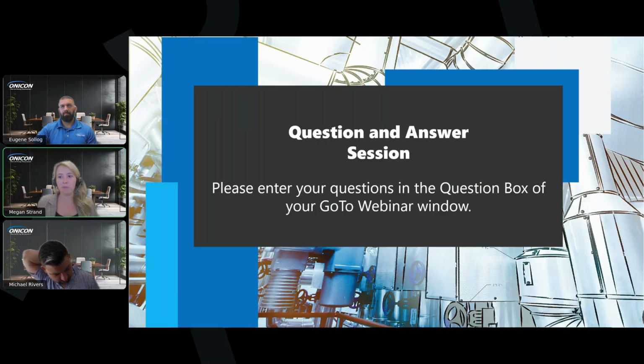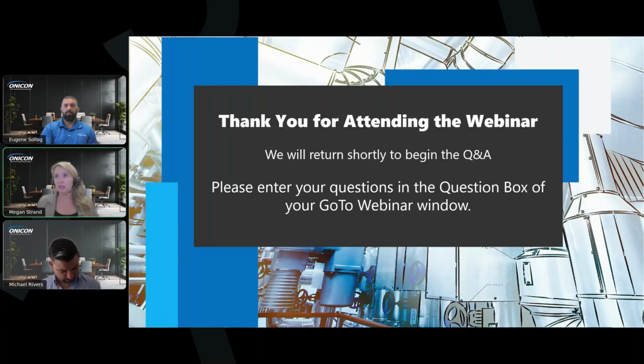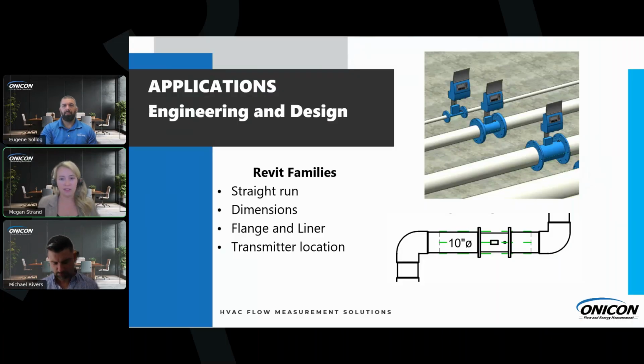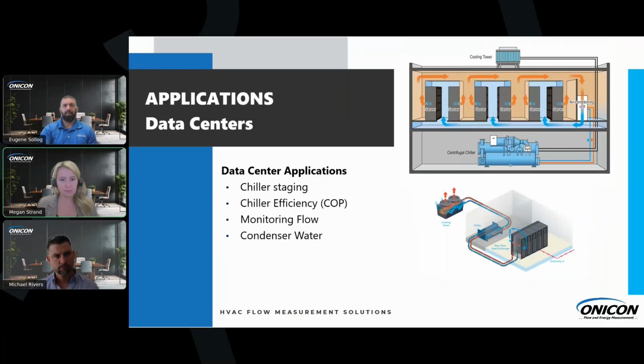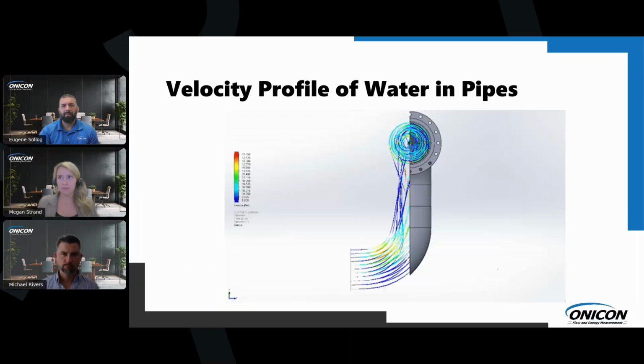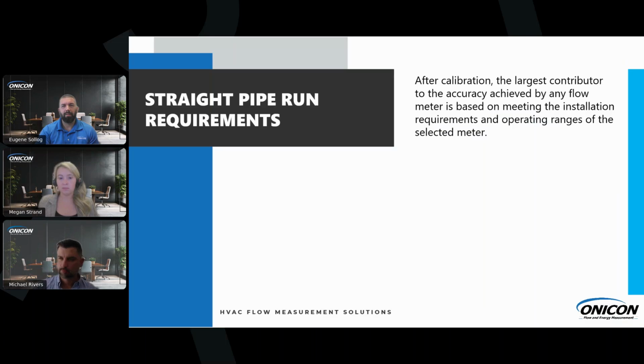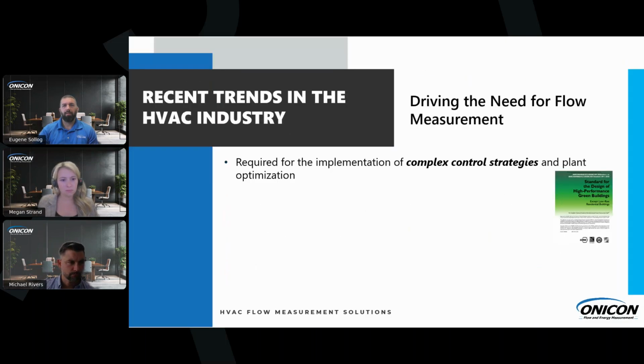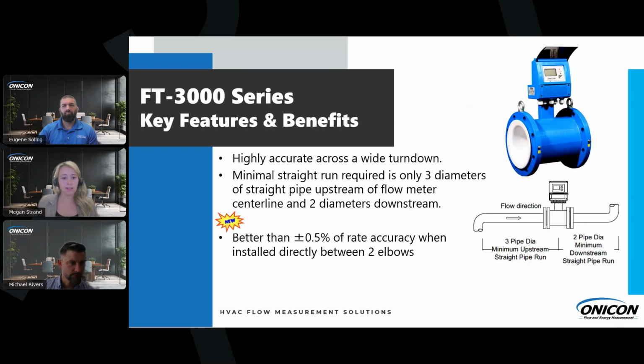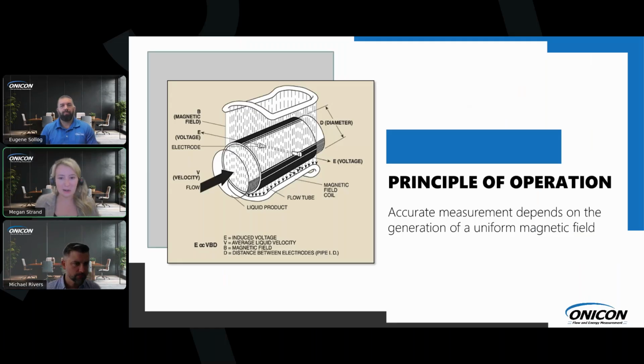So, Gino, can you navigate back to the slide, I think it might be slide 11, that showed a good image of the meter deconstructed? Yeah, no problem. That's it right there. Perfect. Okay, so what I want to highlight here is that all of our meters come standard with two stainless steel electrodes. You can see those in the center. That's what Gino was highlighting. But they also come standard with a stainless steel meter tube, and sometimes you'll see that on the specs. And then the meter tube is covered inside with the liner material.